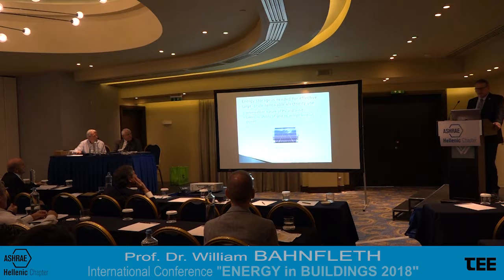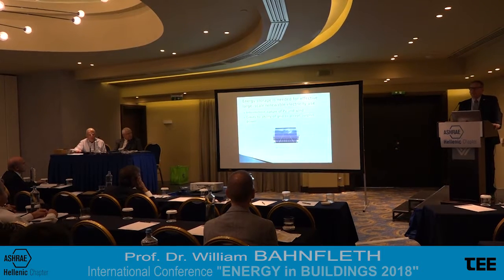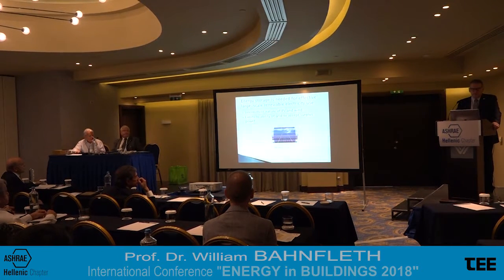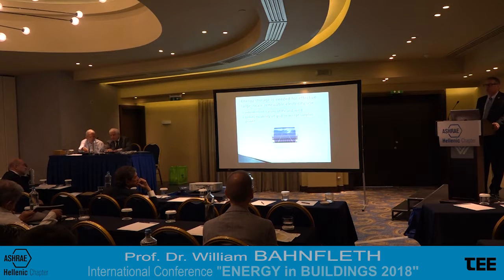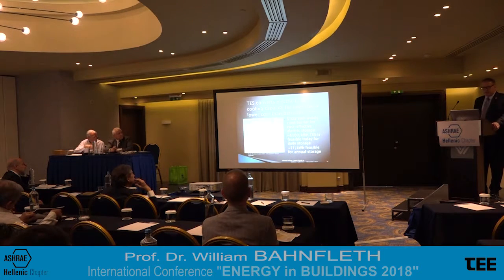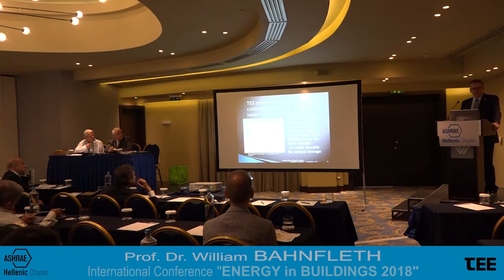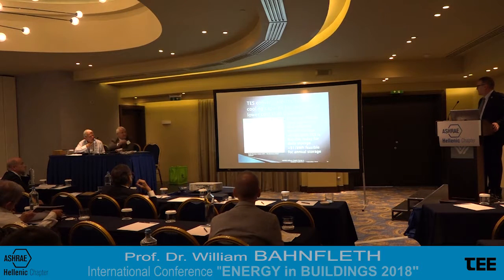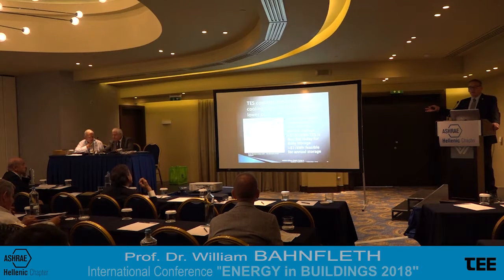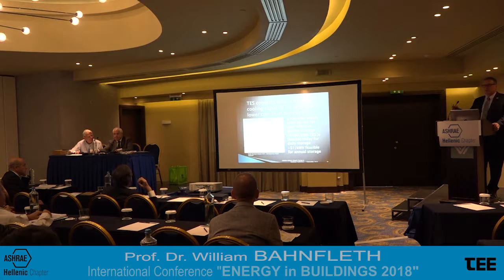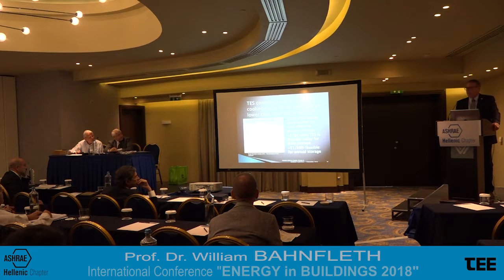And the other issue is storage with batteries that's been widely discussed. And we hear many folks saying that if we could just get to $100 or a little bit less than 100 euros per kilowatt hour, we would be able to make battery storage cost effective. And some of the data that you can find on this suggests that we're pretty far away from doing that. But if you consider thermal storage as being a way of taking electricity that you would have used at one time and putting it away in the form of cooling capacity to use later, we're actually able to do that for $1 a kilowatt hour or less.